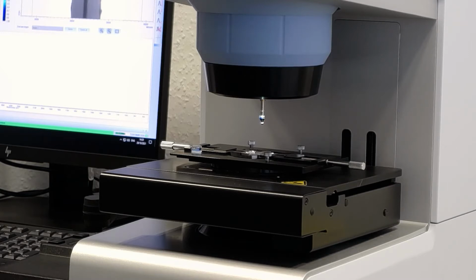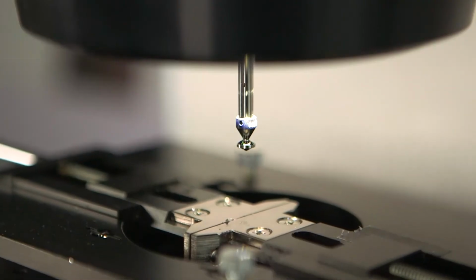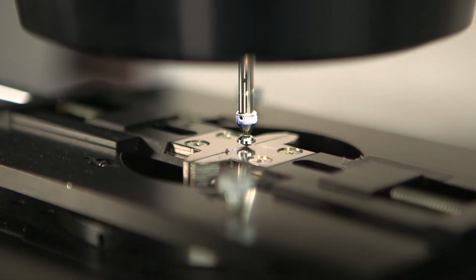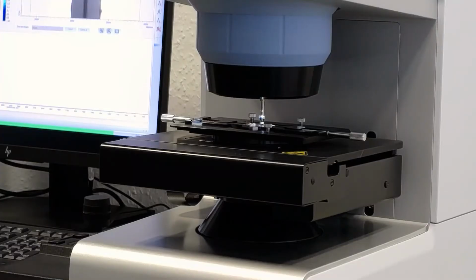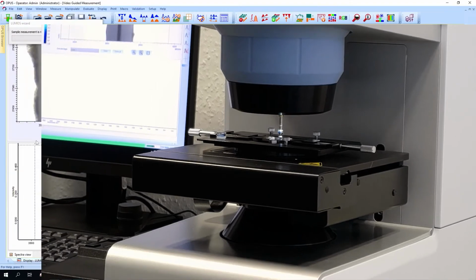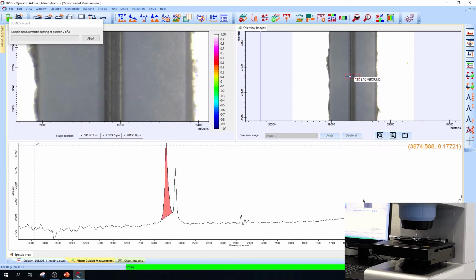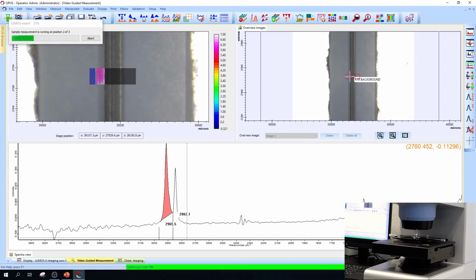When the background measurement has finished, the crystal will move into its focus position with its pressure settings for the pressure between crystal and sample, and the stage is raised and gets in touch with the sample. The stage stops immediately when the pre-selected pressure is reached, and now the very first measurement spot is being collected. We should now get the first spectra after the first tile, after the first 1000 spectra.